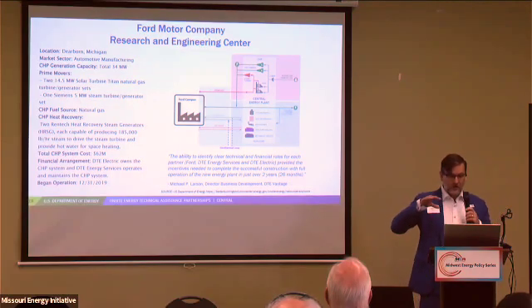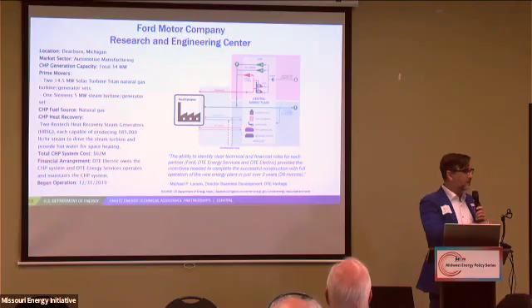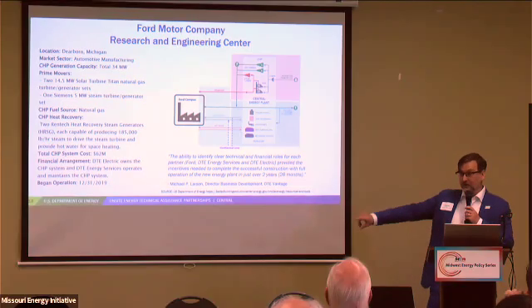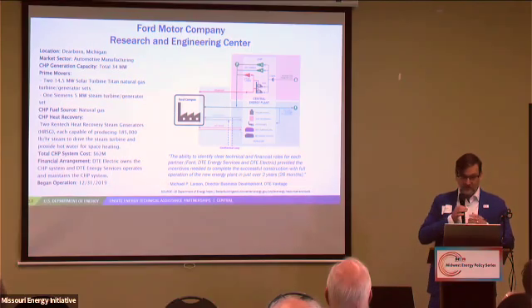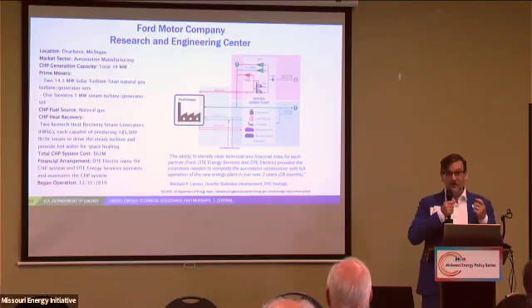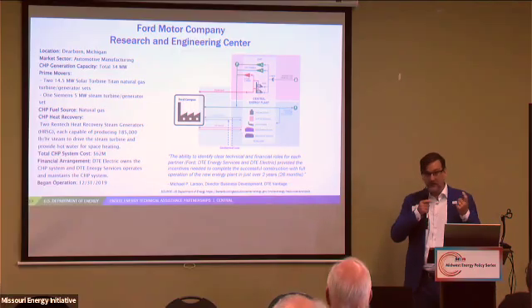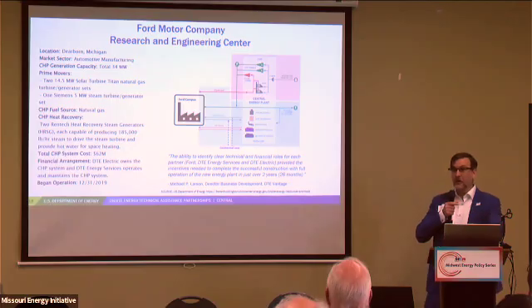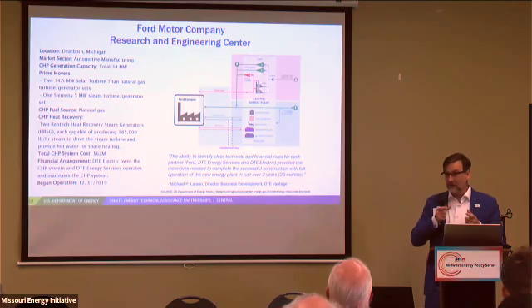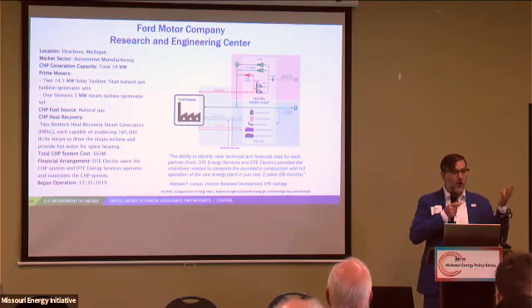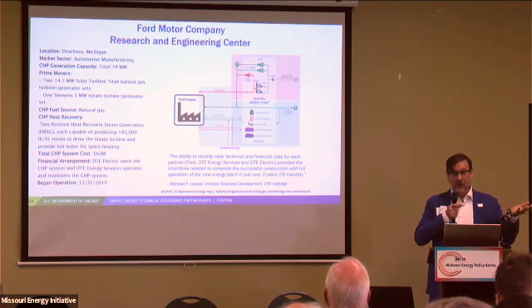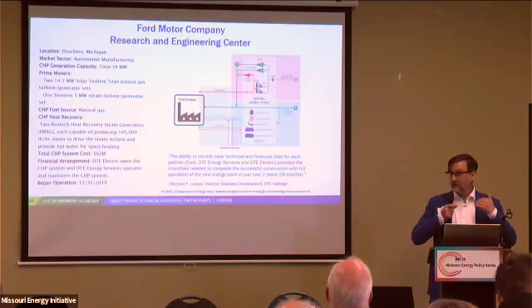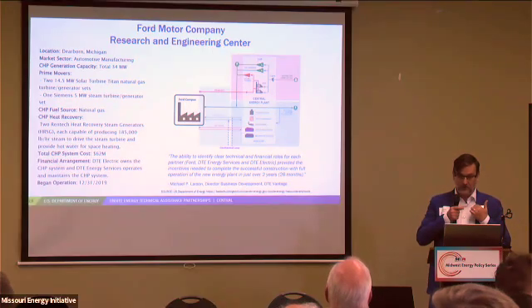So all the electricity goes to the regulated utility, and all the thermal energy goes to Ford. The configuration is such that if the greater utility in Dearborn were to have a blackout, circuits can be shut, so this system could island the Ford plant. It's like having your own power plant that the utility owns, but if the utility grid were to go on a blackout, that plant would still be operational and still serve your load.